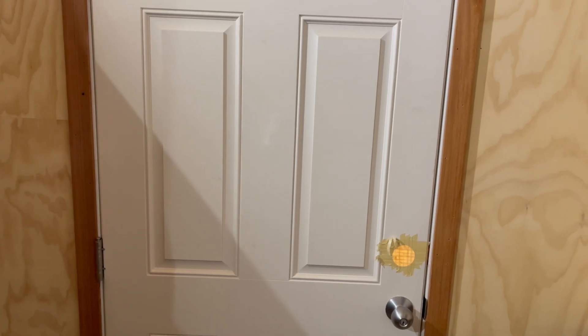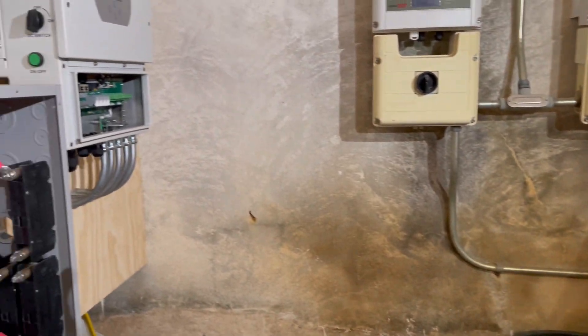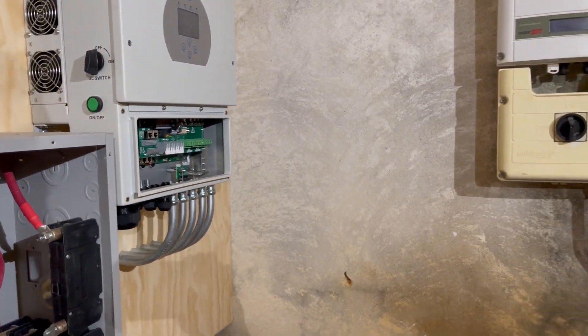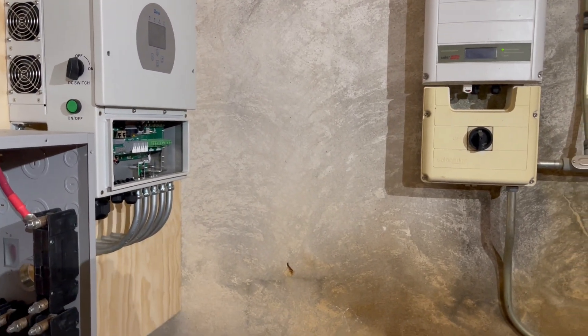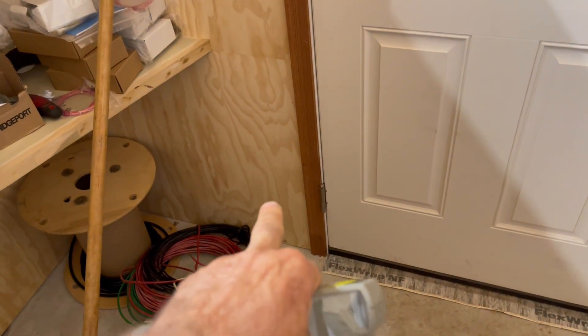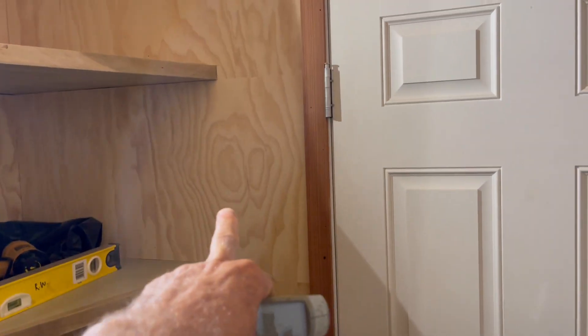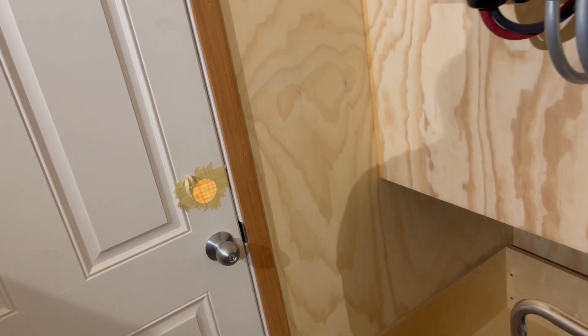The temperature of the surfaces inside the building when I came in this morning were about 58 degrees. I came out about nine o'clock this morning and closed that off. The concrete wall was about 63 degrees — it had been warmer, so basically it was losing heat into the space trying to keep it warm. The surfaces in the room were 55–58 degrees. It was colder down at the bottom because the cold air was spilling in and spreading across the floor — about 53 degrees down low, 58 degrees higher up. The door was about 56 degrees, all because of air infiltration.